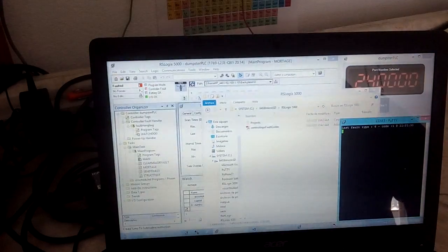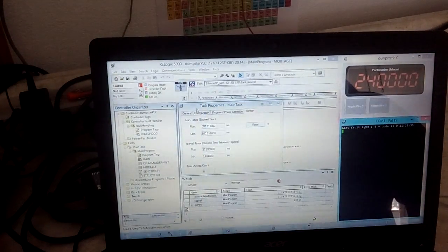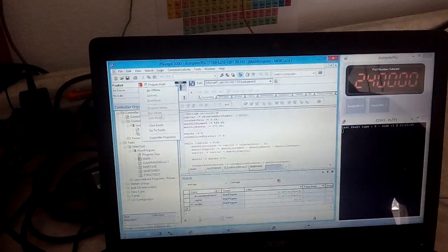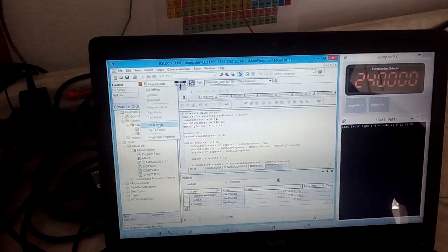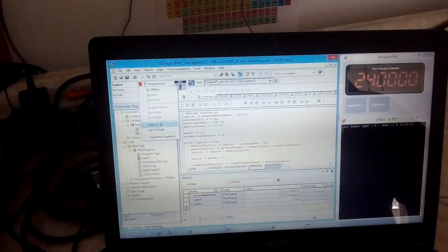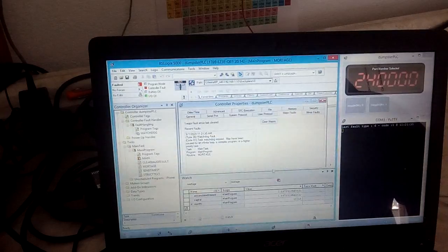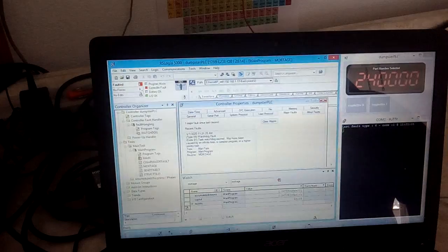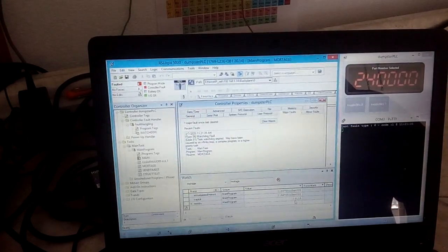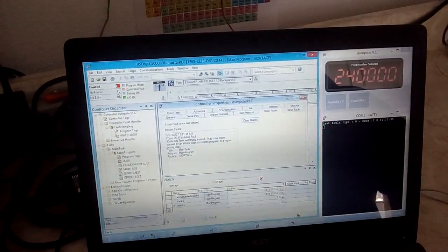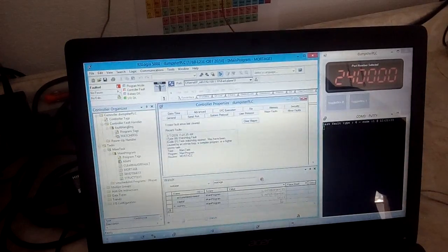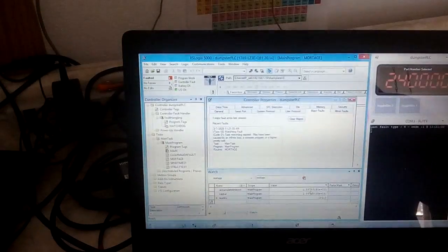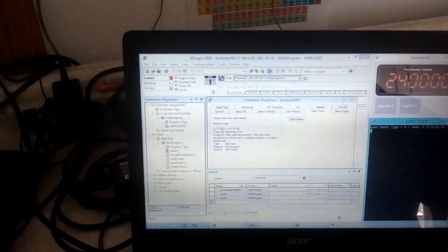So what happened is that if you click here on the PLC faulted running taskbar, you go to not clear faults, but go to faults and look at the major faults. It says the routine MORTAGE caused this. It took too long. Imagine this calculation taking 18,115 iterations to complete. It exceeded 0.5 seconds. That's why you're getting that.